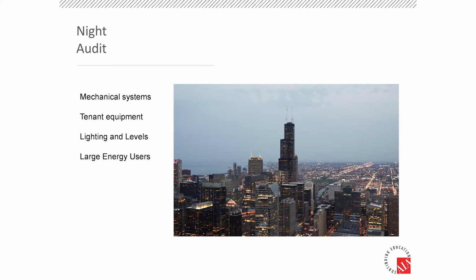What we're doing during the night audit is we're looking for mechanical systems while they're off. We can climb into an air handling unit and look at the ductwork, see the state of it, look at filters, are they being changed, motors, belts. Is there equipment that is manually overridden in hand at the unit? Is there other equipment that's running when it shouldn't? What are the spaces doing? Are the lights on or off when it's unoccupied? And what are the levels of that lighting?